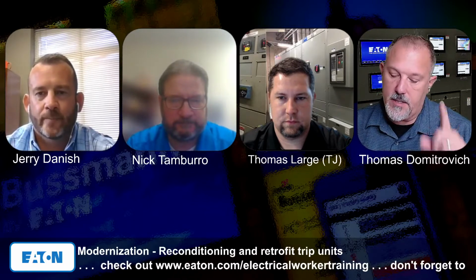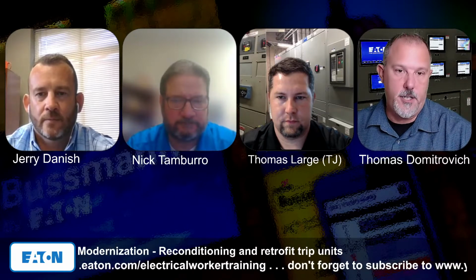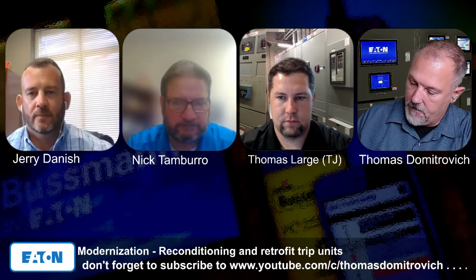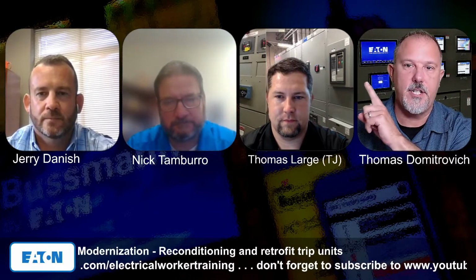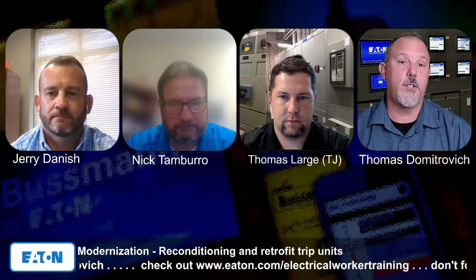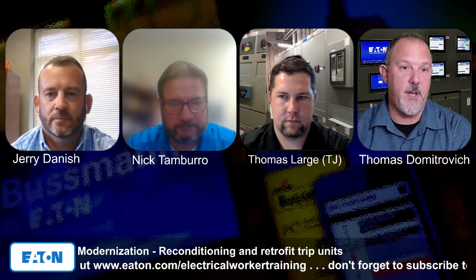So the first discussion point has to be what is reconditioning, right? Article 100 gives us a definition of reconditioning, and I'll read it for everybody. Electromechanical systems, equipment, apparatus, or components, and that's pretty comprehensive, that are restored to operating conditions. That's an important part of the pie, because of that breaker right behind TJ's head. If it is in working order and we remove it and replace the trip unit, I don't know that we've technically met the definition of reconditioning, because we have instructions for retrofitting, right? So taking that brain and putting a new brain in, is that part of the manufacturer's instructions?